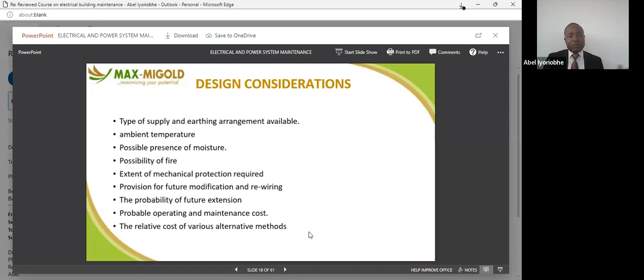So electrical maintenance cannot be overemphasized. The first consideration is the ability of a cable to carry its required load. As I told you, when sizing your cable, after carrying out your load analysis, you're able to determine the size of cable required to power your equipment. If you use an underrated cable, you're going to spend three times fixing that problem. It's better you get it right. If you don't know how to do it, get experts to help you out so that you don't spend twice.